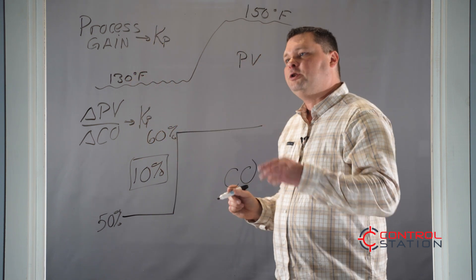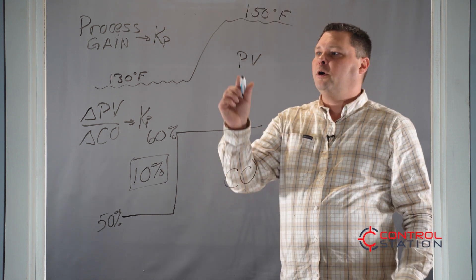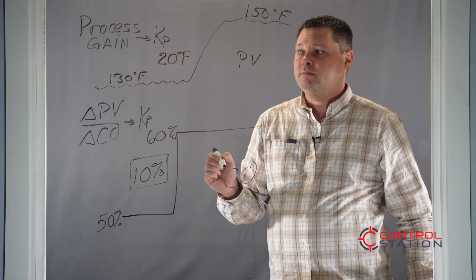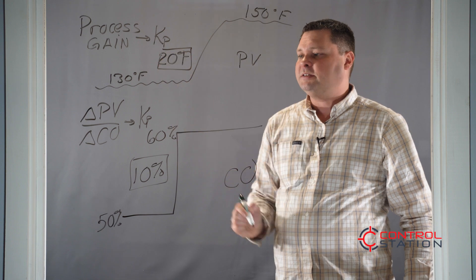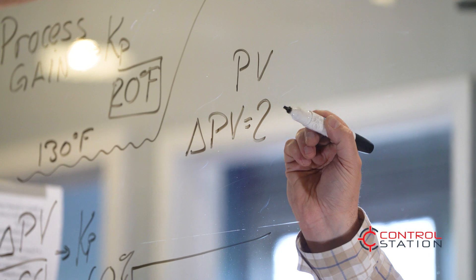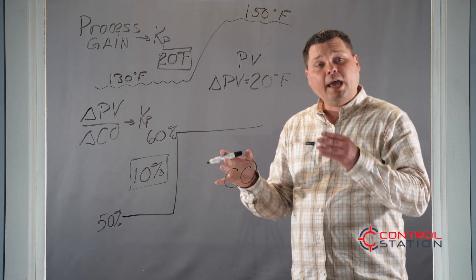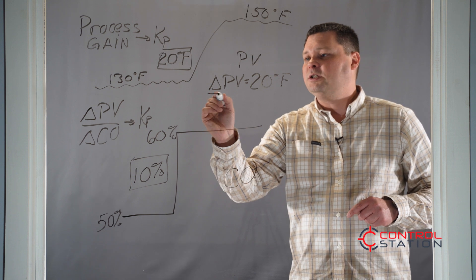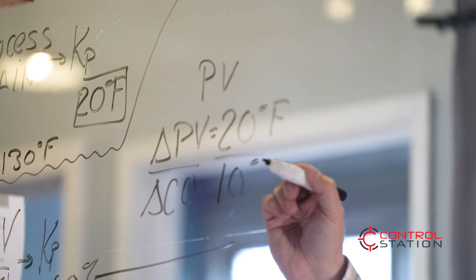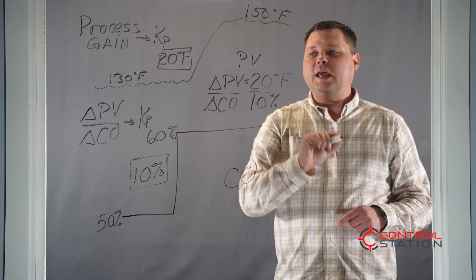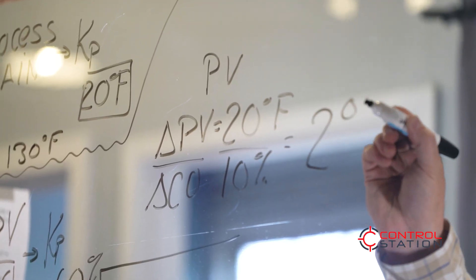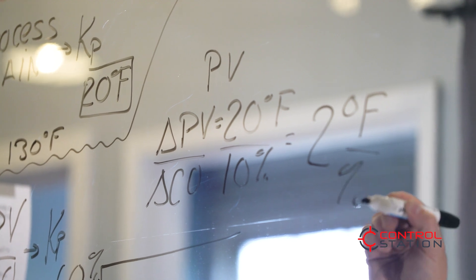In this example the process variable goes from 130 to 150, which is a change of 20 degrees Fahrenheit — our delta PV is 20 degrees F. We divide that by the change in the controller output, which is 10 percent. So 20 divided by 10 gives us 2 degrees Fahrenheit per percent CO.